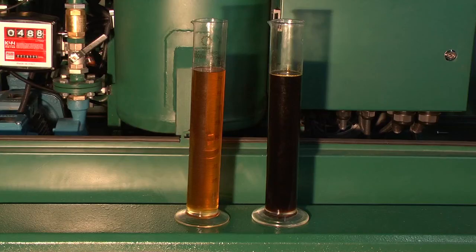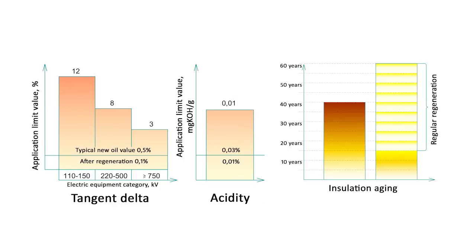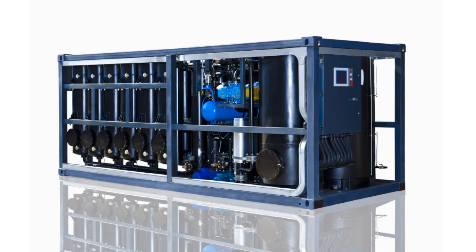This technology surpasses the existing systems in both quality of oil treatment and ease of servicing. The ability to treat the oil directly in the transformer is an additional advantage. Using the same sorbent many times saves labor costs related to sorbent replacement and eliminates storage and disposal costs. The efficient sorbent reactivation technology keeps electric energy costs very low. The system can be placed on a separate trailer or in a standard 20 or 40 foot container, and can be used as a stand-alone application. The Fuller's Earth oil regeneration technology is widely known and used worldwide due to its high efficiency.